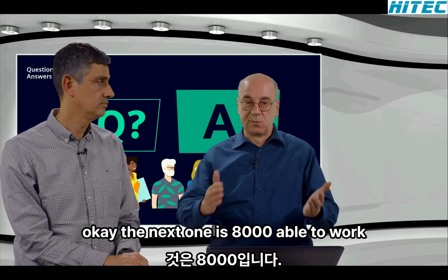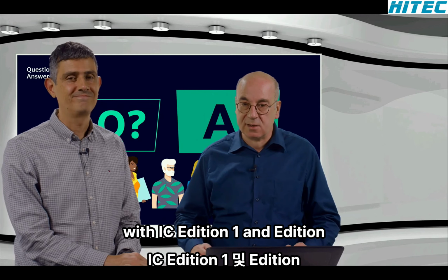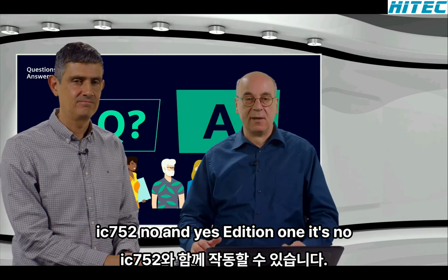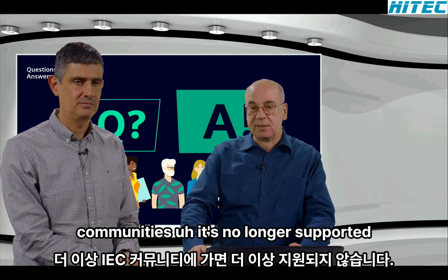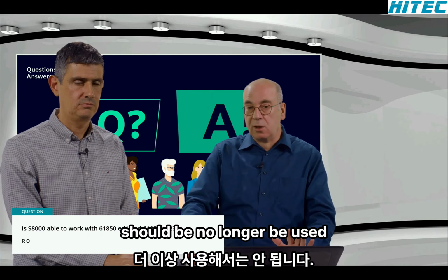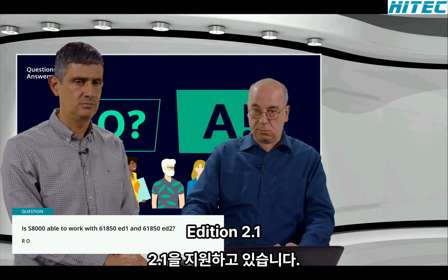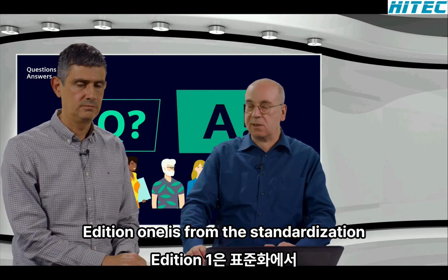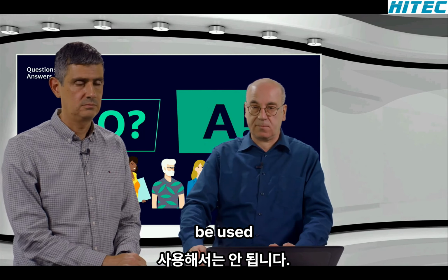Okay, the next one: is S8000 able to work with IEC edition 1 and edition 2? No and yes. Edition 1 is no longer supported by the IEC communities and should no longer be used. So we are supporting edition 2 and edition 2.1. Edition 1 is no longer supported by the standardization body and should not be used.